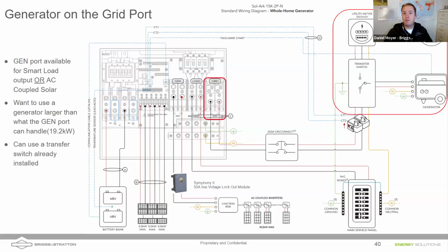One thing we can use is one of our Symphony II load management modules and set it for lockout. One of the John Cromer has addressed this. Even without the AC coupled solar, we might have DC coupled solar on there, and we could start backfeeding the grid. I think another testament to how well Sol-Ark can integrate with the generator is that the Sol-Ark will recognize that if it sends back to the grid and it happens to be a generator, it will see the frequency and voltage start to fluctuate more than it should had it been the grid, and will curtail that backfeeding of the generator. Right, we don't want to burn out the generator.